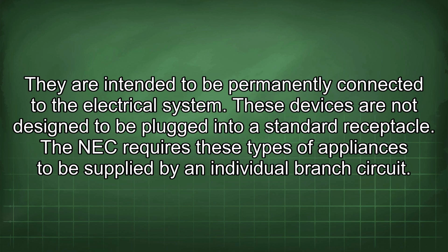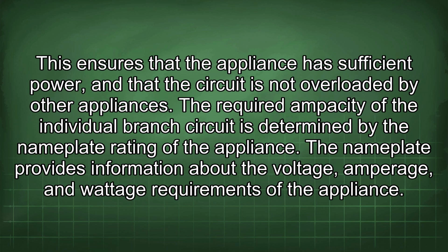The NEC requires these types of appliances to be supplied by an individual branch circuit. This ensures that the appliance has sufficient power and that the circuit is not overloaded by other appliances. The required ampacity of the individual branch circuit is determined by the nameplate rating of the appliance. The nameplate provides information about the voltage, amperage, and wattage requirements of the appliance.